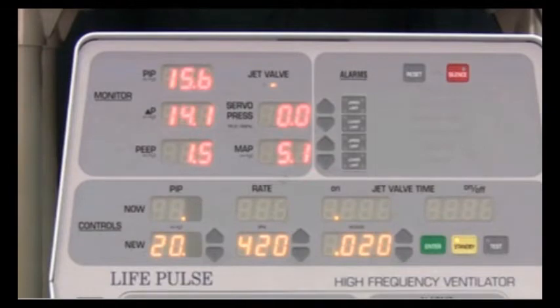While the ventilator is in the standby mode, the update is a 10-second update. So it will take about a minute, minute and a half for the monitor to equilibrate and display an accurate PIP, PEEP, and mean airway pressure being delivered by the patient's current ventilator. The important thing to remember is that the LifePulse, while in the standby mode, serves as a ventilator monitor. It's monitoring whatever ventilator the patient happens to be on as you're preparing the LifePulse.